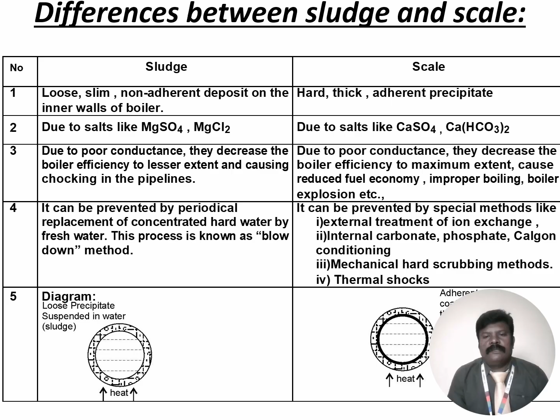Sludge can be prevented by periodical replacement of concentrated water by adding fresh water. This process is known as blowdown method. Blowdown is the process of removal of concentrated water frequently by adding fresh water. Scale can be removed by some special techniques. The scale cannot be removed by blowdown operation, but it can be removed by special methods like external treatment by ion exchange and the zeolite process, and internal conditioning like using sodium carbonate, sodium phosphate, calgon conditioning, etc. Then the mechanical scrubbing method, then the thermal shock method.